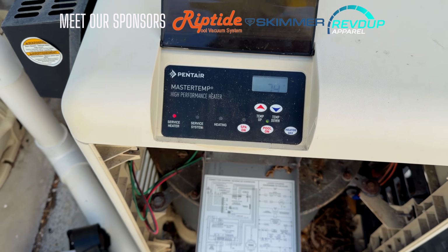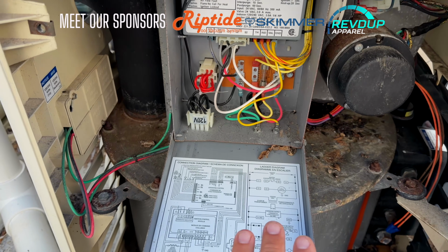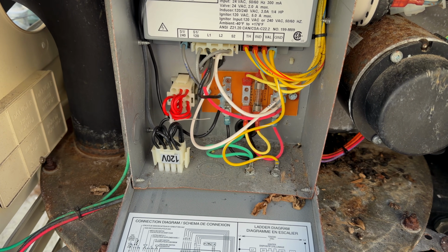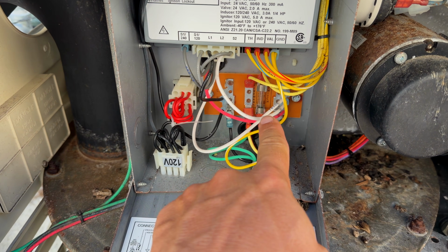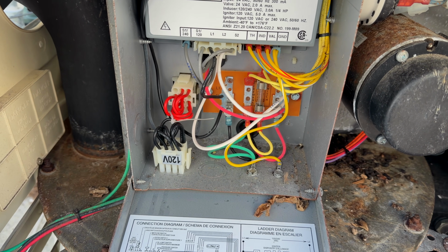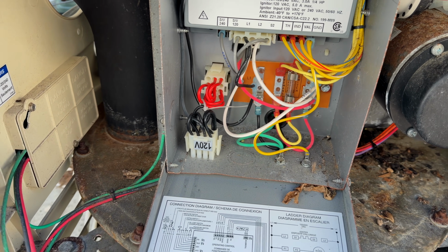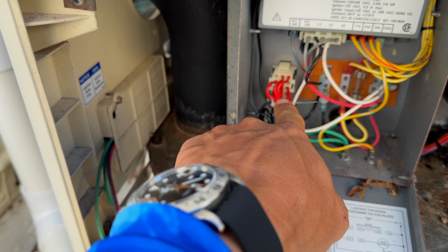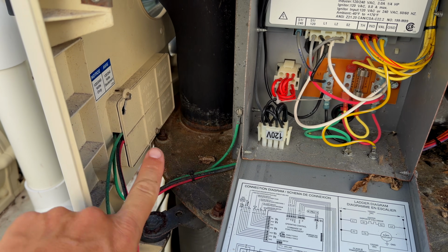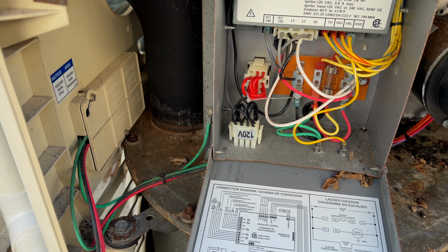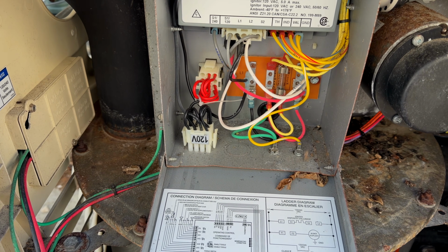But you can clearly see here that there is a service heater light lit up, so the heater's not firing for some reason. So what you want to do first is open up this electrical box here. Make sure that everything's copacetic. Make sure that the fuse isn't blown here in the fireman loop. You want to make sure that fuse is in good shape. And then you want to make sure the plug that's plugged into the heater matches the incoming voltage, which this does.